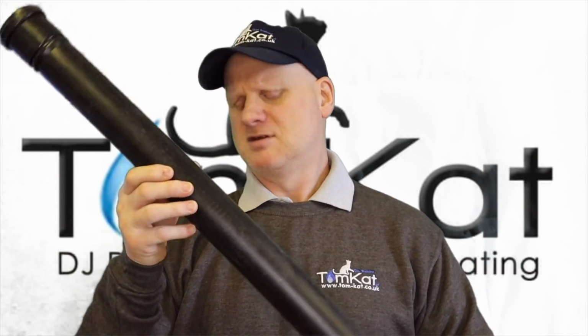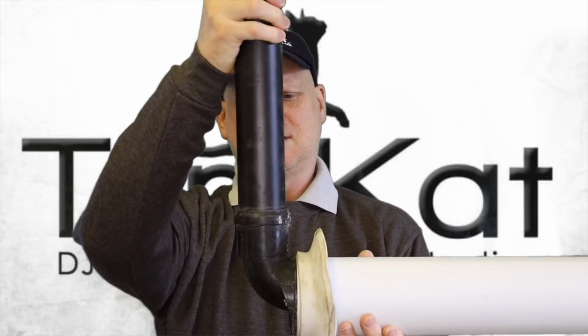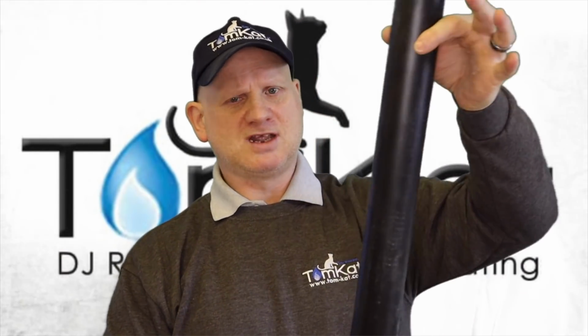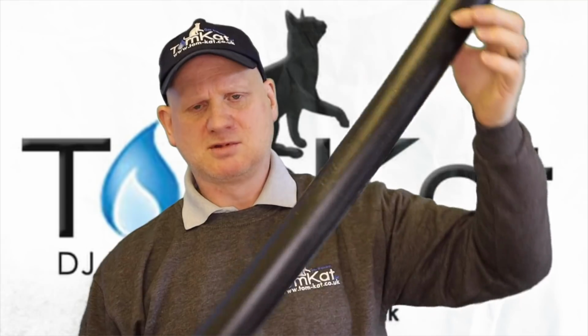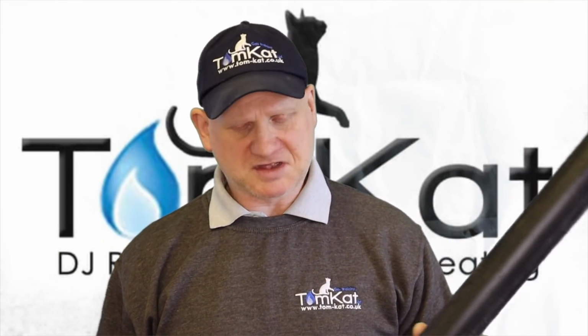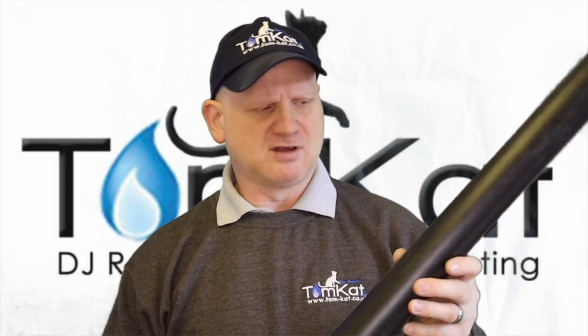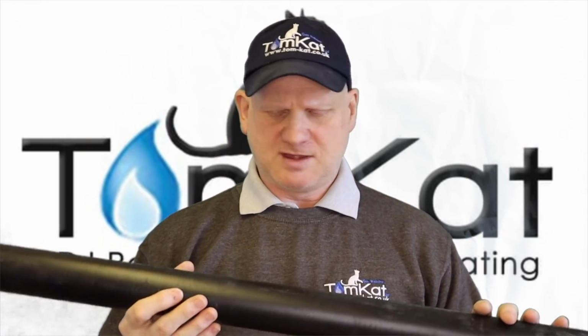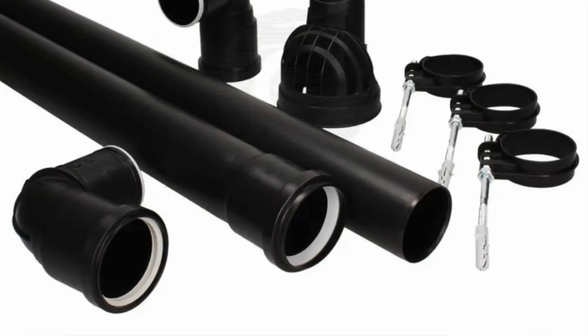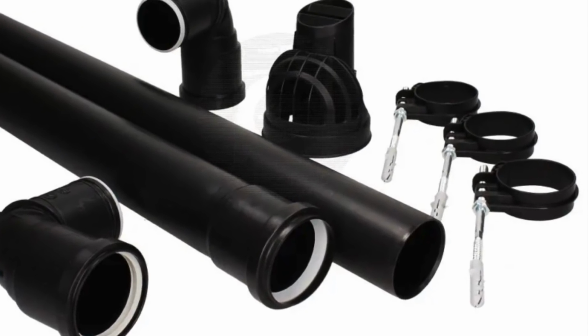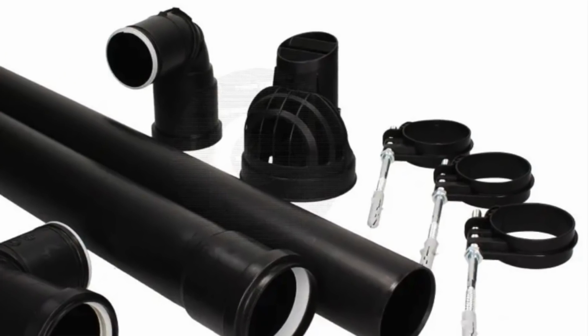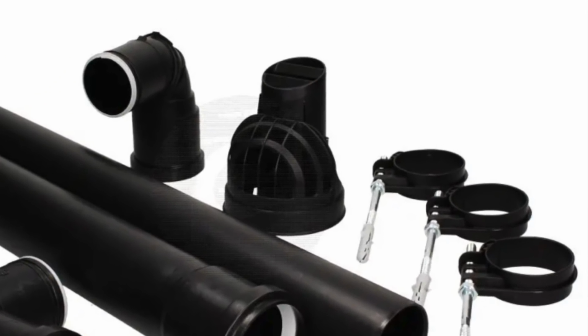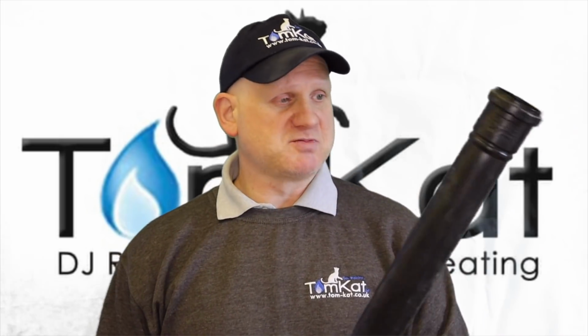But the standard pipe after the elbow would just slot into there, it's just a push fit. They come in meter lengths, but you will need to bracket them top and bottom. So the standard plume kit normally comes with your turret, elbow or whatever, the terminal, this pipe, a couple of clips, and then it normally comes with an elbow on the top which you can turn, obviously no more than 45 degrees to the wall. So that's your plume management kit.